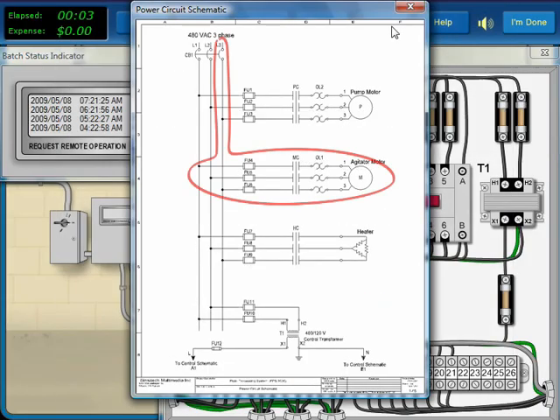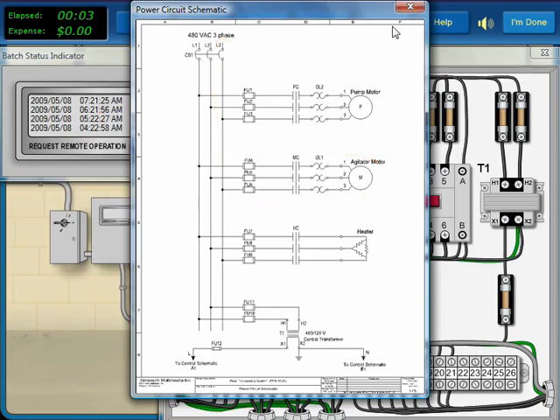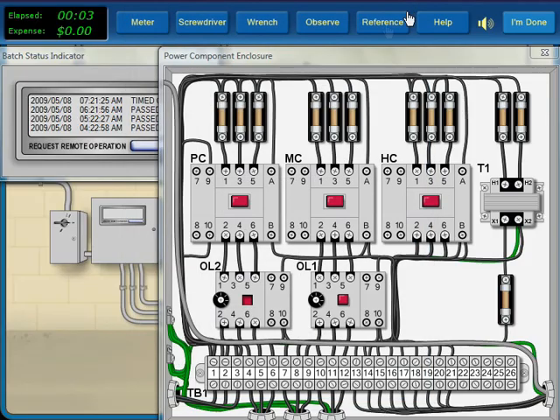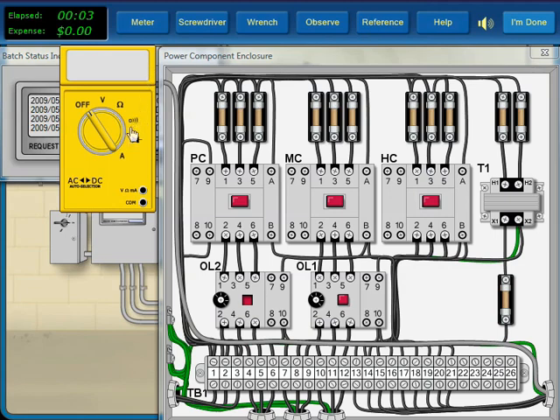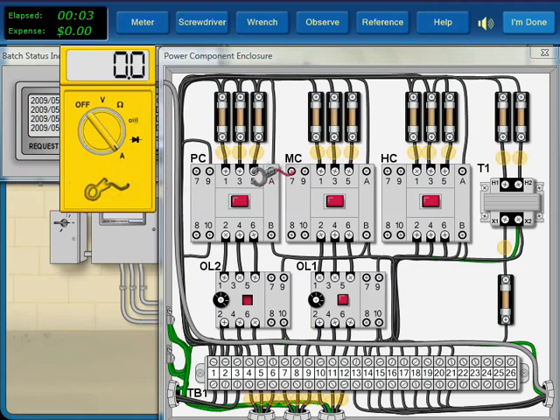Based on this, we need to reduce the problem area by testing. Because the overload trips, we know that there is excessive current in one or more phases. Therefore, our first test is to use the ammeter to measure the current in each phase.